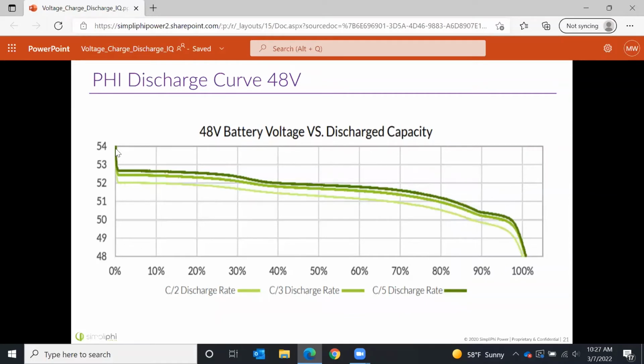As soon as you apply a large load, let's look at the C/2 discharge rate first. That voltage is going to heavily drop, maybe down to 52 volts, then it's going to stay very, very steady, not even reaching 51 volts until you're at 30% state of charge remaining. So it's extremely difficult to look at the voltage of this battery and know how much capacity you have left.